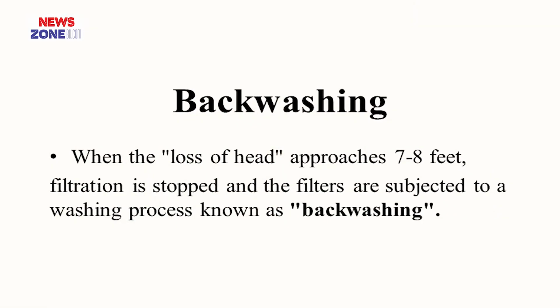As filtration proceeds, the suspended impurities and bacteria clog the filters. The filters soon become dirty and begin to lose their efficiency. When the loss of head approaches 7 to 8 feet, filtration is stopped and the filters are subjected to a washing process known as backwashing. Now we see what is backwashing. Already I said that when the loss of head approaches 7 to 8 feet, filtration is stopped and the filters are subjected to a washing process known as backwashing.